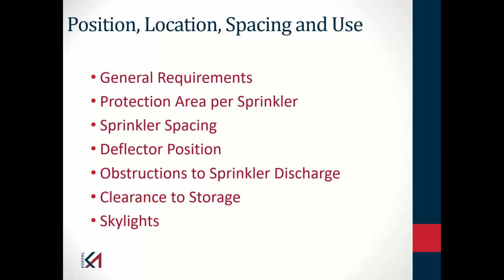For example, a steel I-beam can be an obstruction. A bar joist can be an obstruction. We can have floor-mounted obstructions, such as partial height partitions in an office area where I need to get the water over top of the obstruction. Again, with the intent that I need to wet most of the area.